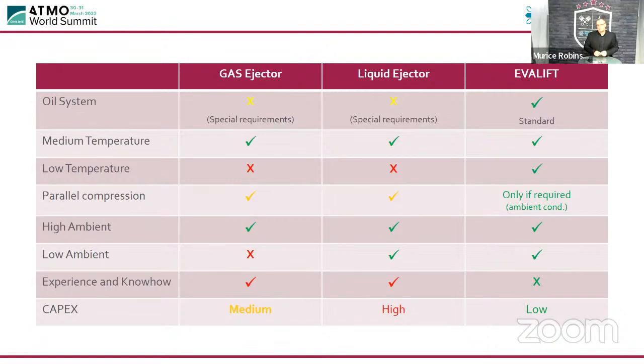All of the ejectors and EVALIFT can all work with medium temperature and low temperature. You can't use a gas ejector, you can't use a liquid ejector, but on EVALIFT, you can use low temperature. So you're getting the savings from low temperature and medium temperature. Parallel compression is needed for gas ejectors and liquid ejectors. For EVALIFT, if the ambient conditions call for it, then you can have a parallel compressor to add to your savings. But if the ambient conditions don't call for it, then you don't have to put it in, but you can still use the EVALIFT system. In high ambient conditions, gas ejector, liquid ejector, and EVALIFT all work, so everybody's happy. In low ambient, the gas ejector doesn't perform and is not used. The liquid ejector can perform in low ambient, but so can EVALIFT.